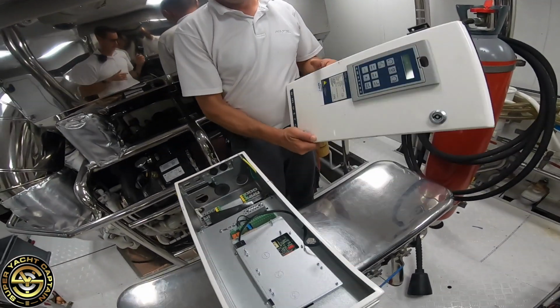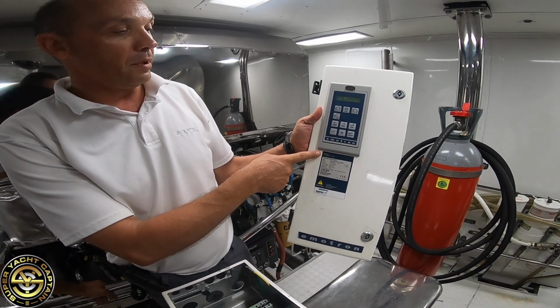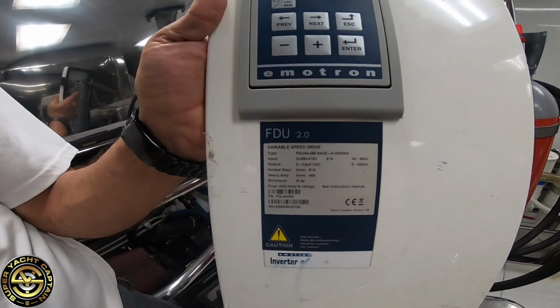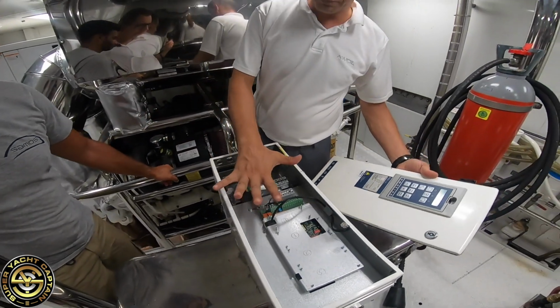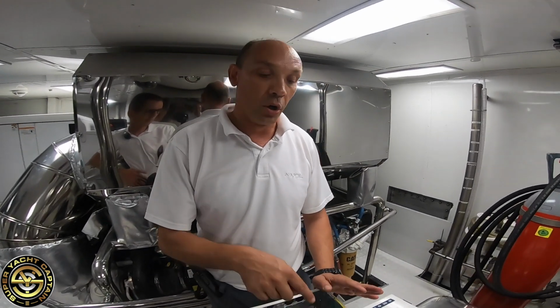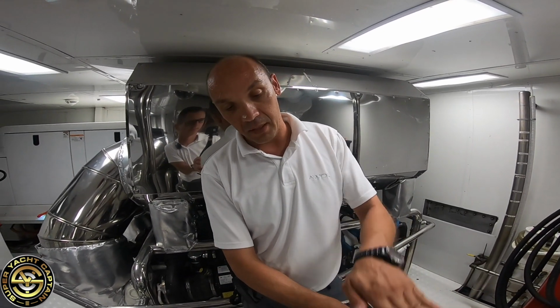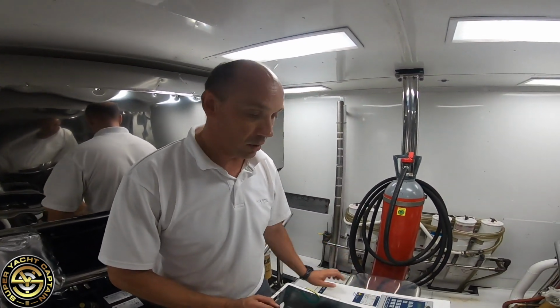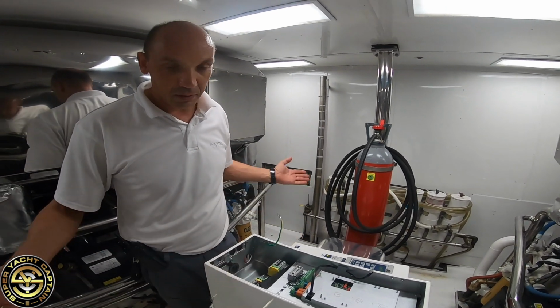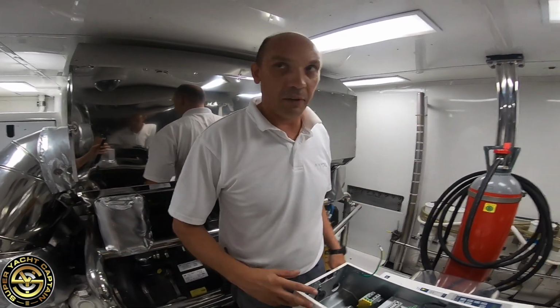Right, Slav, so this is the old box here. So this is the old box, a VFD, variable frequency driver. This is the specification of the control box and the main box. In this box here, we have three boards. The main power port is on the aft, right back. So main board, middle, and then coming the connection for the control. Now Francesco will check, and I think we just need to replace it. Connections are all the same, just plug and play.